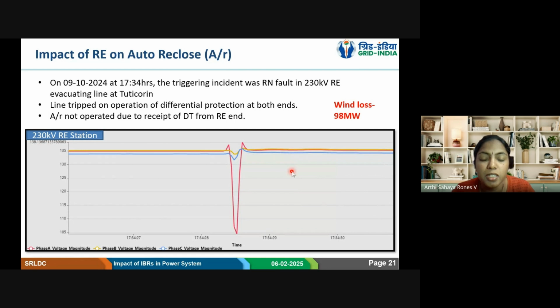So the problem comes when we have only one RE evacuating line. If we have two lines, anyway, through grid end, even the RE connected end, there will be fault contribution. So auto recloser operation also can happen. So in single evacuating line, the issue is, what RE developers are telling is they will lose the reference voltage. So if one phase is not available, my PLL will not have a reference voltage. PPC will not have a reference voltage. So operation cannot happen. It will trip, inverters will trip. That is what they say.